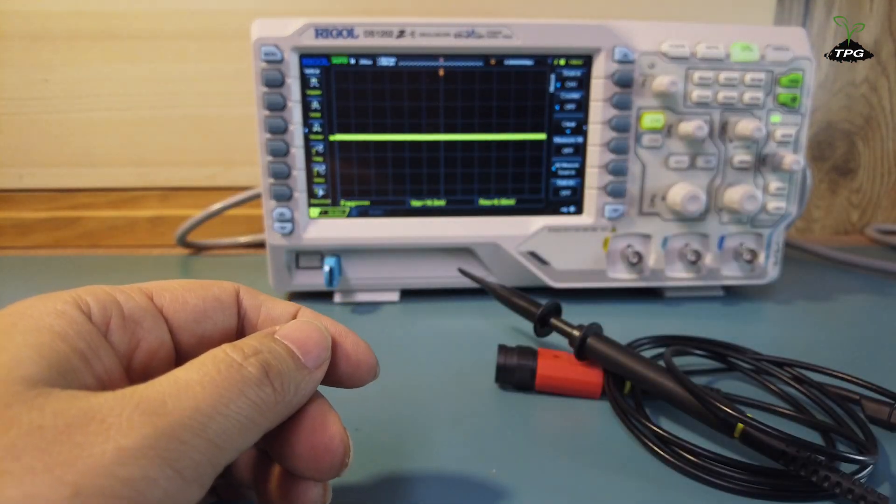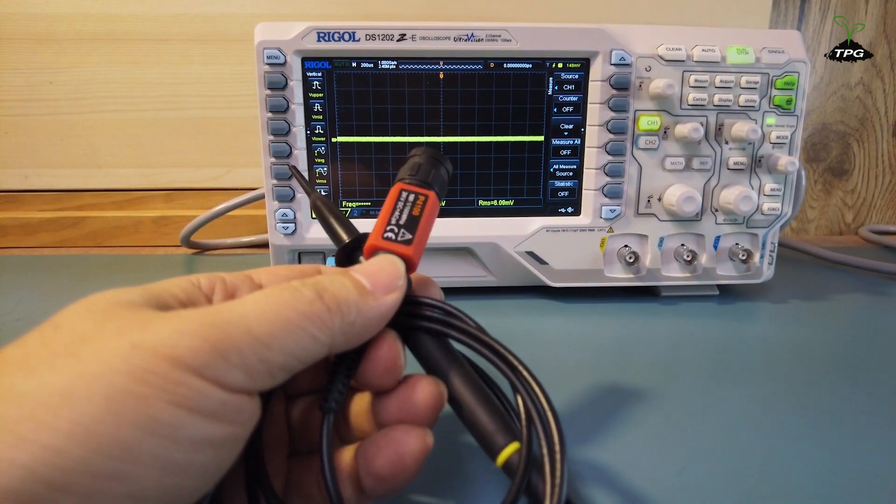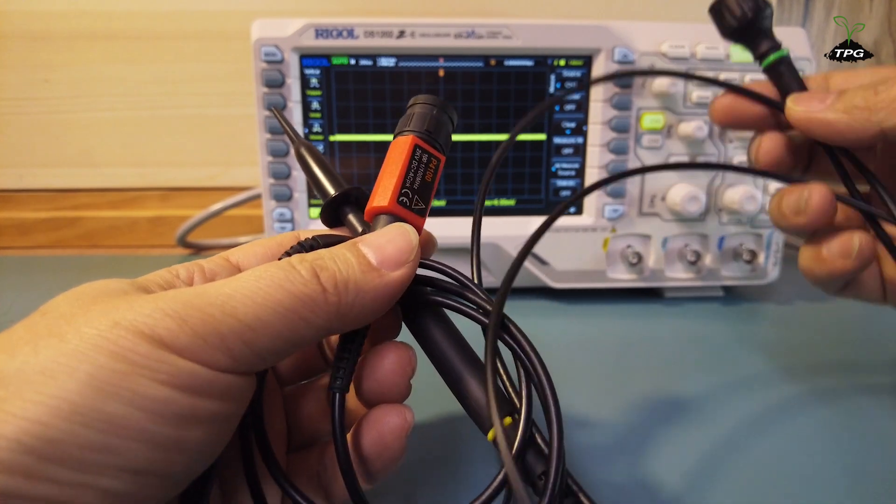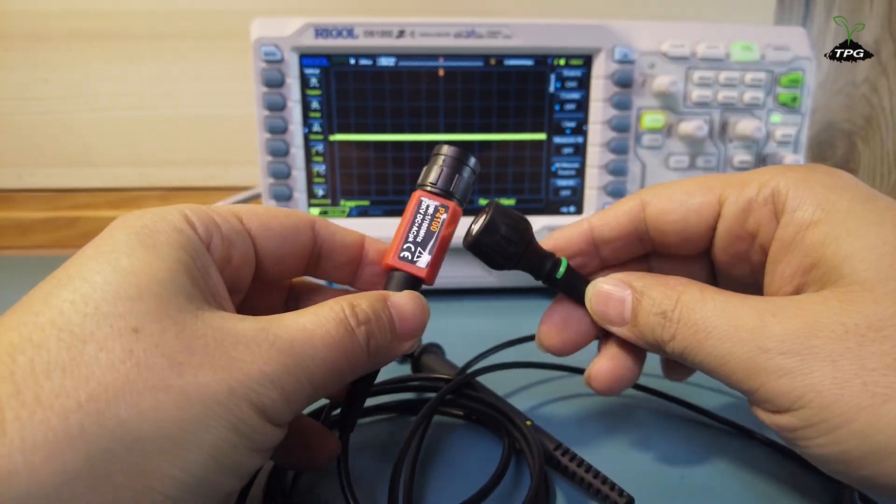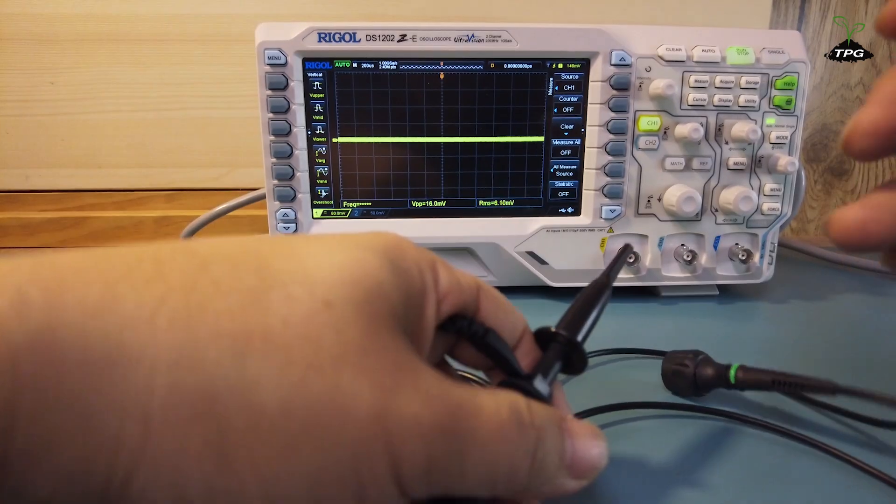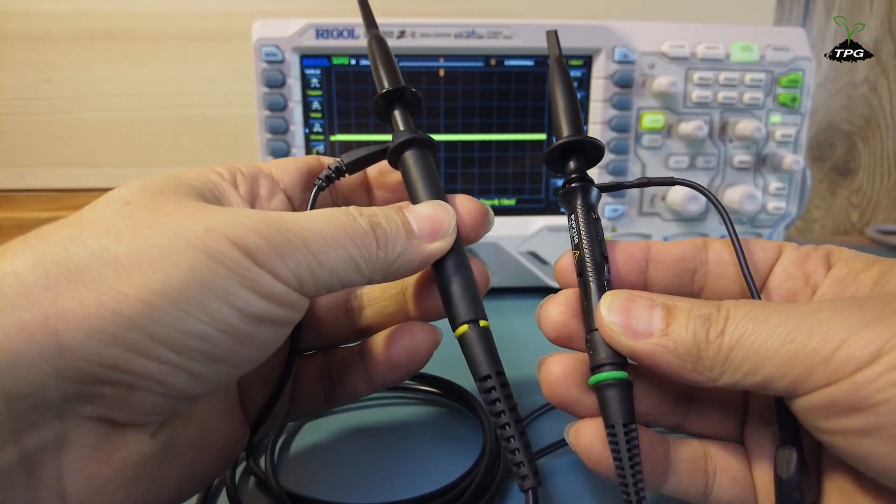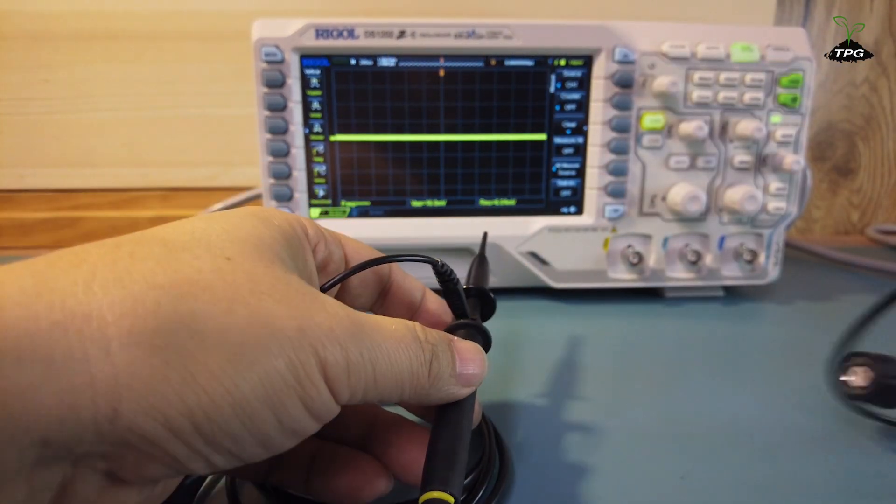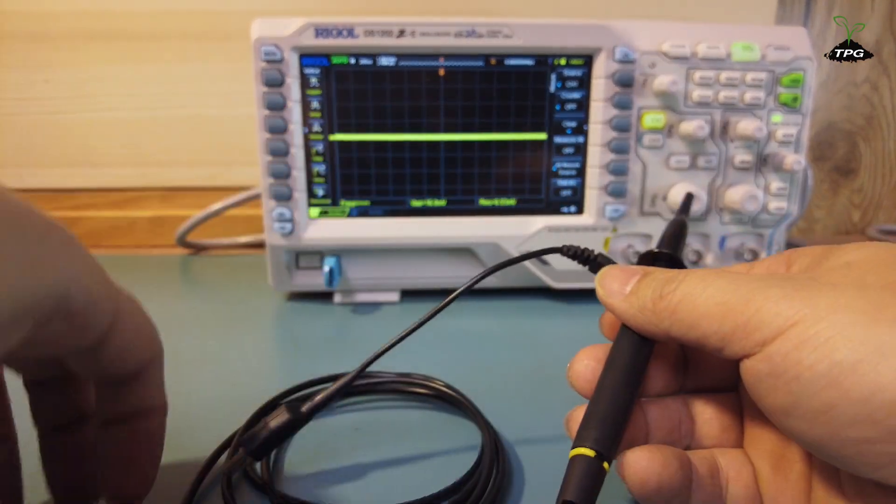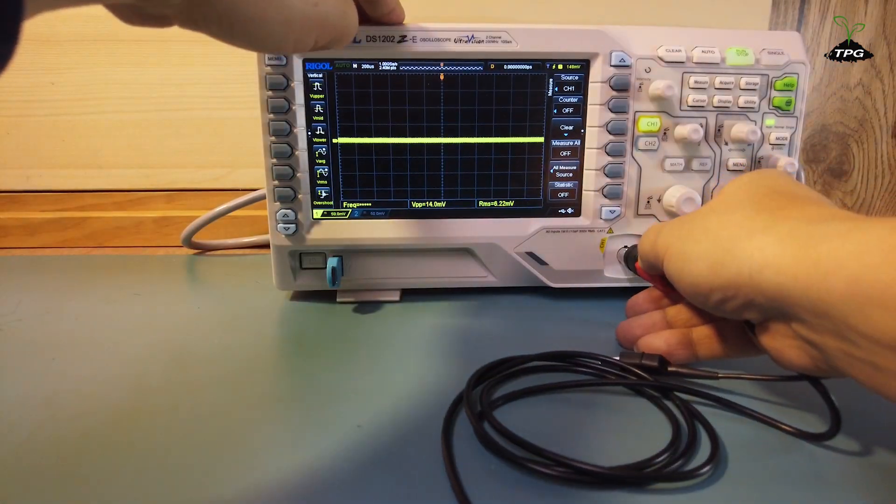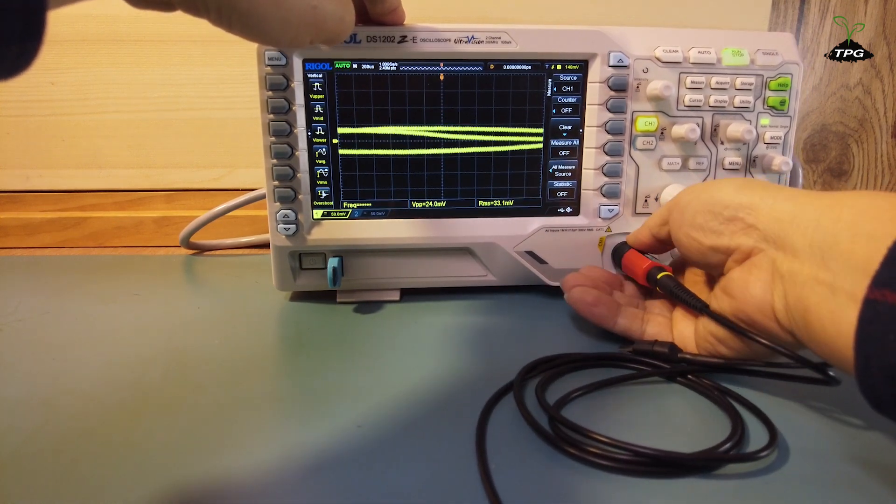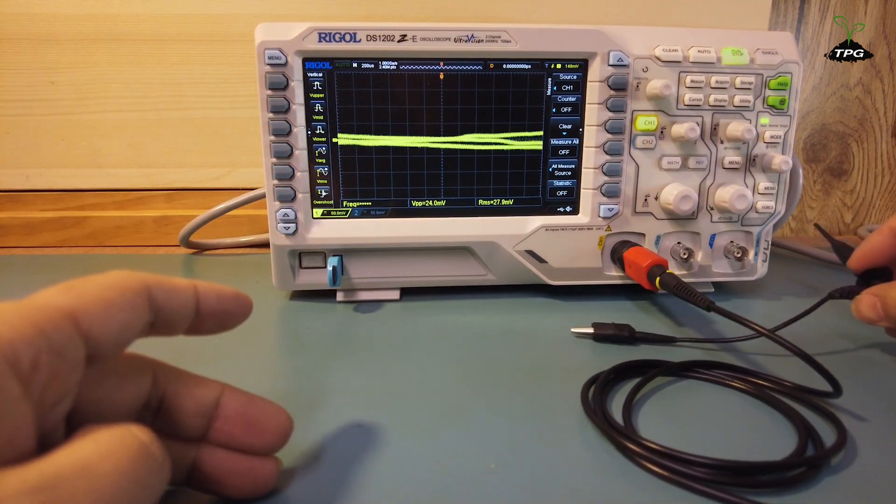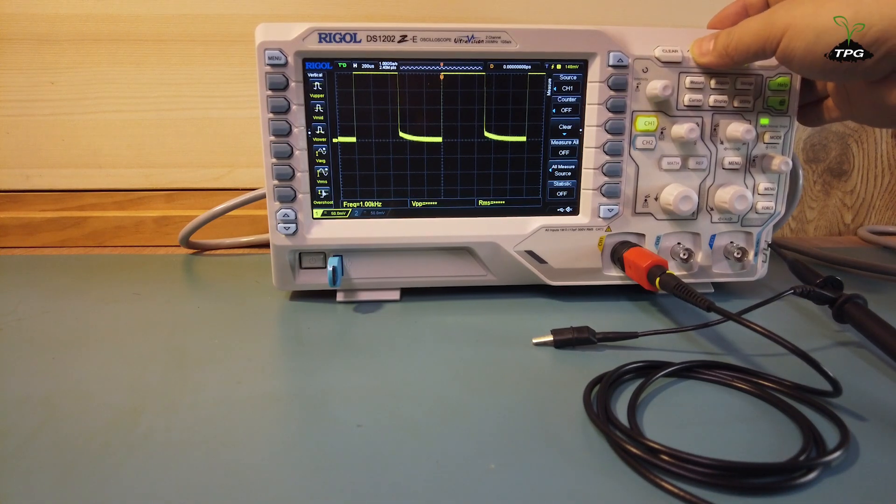Compared to standard probes, such probes are physically large to prevent high voltage arcing. Before taking a measurement, check the probe compensation and adjust it to match the channel input.